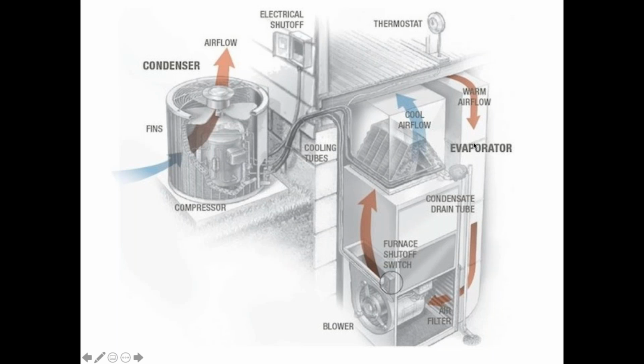So all of the air in the house is going through this furnace. Sometimes you're heating it using a gas heat exchanger. It's got a radiator in it. You burn gas inside the tubes of that heat exchanger, and then they get exhausted outside. But on the outside of those tubes, you put the home air, and you can heat it in the wintertime. And in the summertime, you turn that part off and you just run the air conditioning, so you cool the air with these coils.